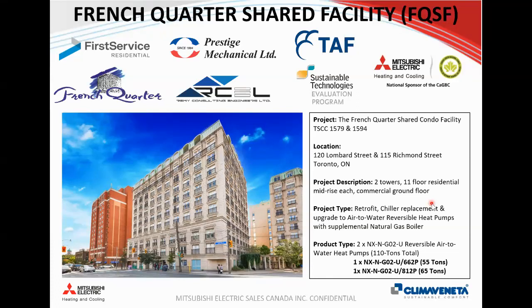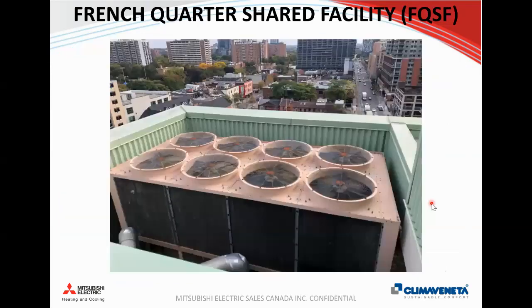But essentially they had an air-cooled chiller that needed to be replaced, and the condo board was forward thinking, and instead of replacing it like for like, that's a fixed asset where there's no rate of return. But with the heat pump sized for cooling, they can get as much heat out of the machine in the winter when it makes sense to do so, whenever they would normally shut off that chiller. So their existing chiller was kind of in a small enclosure on the penthouse, and this was a 110-ton chiller.